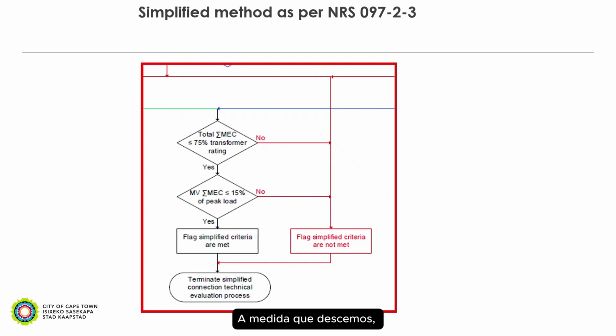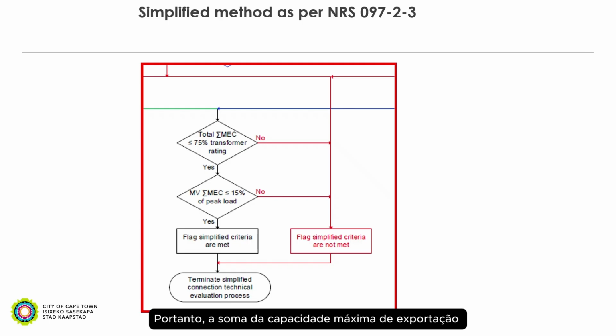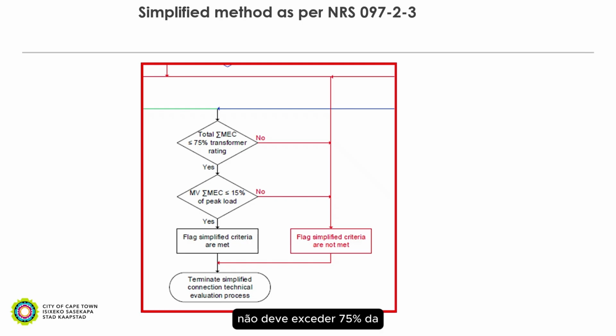Then as you come lower down, we also have other criteria in terms of the upstream transformers. So the sum of the maximum export capacity should not exceed 75% of the transformer rating, as well as the sum of the maximum export capacity on the MV feeder should not exceed 15% of the peak load. If you meet that criteria, you can basically proceed with the installation. If not, a red flag needs to be put onto that system, and further studies or network upgrades might be required to be able to facilitate that connection.